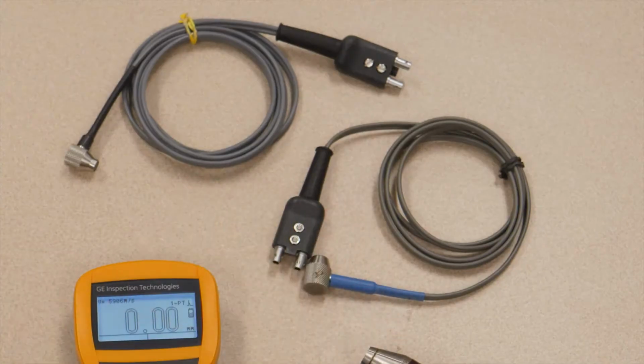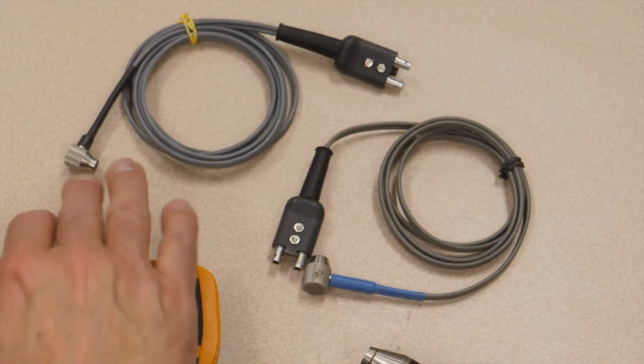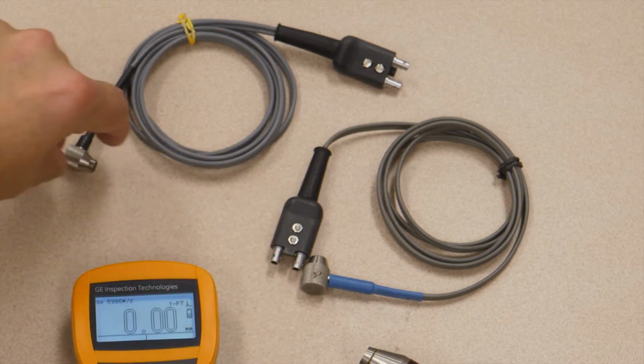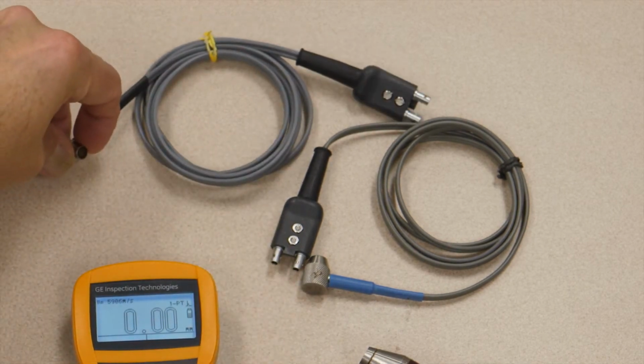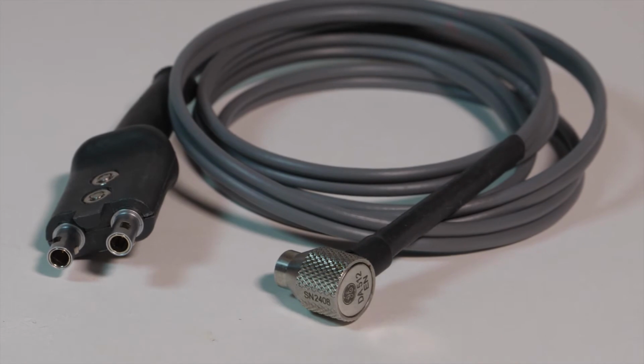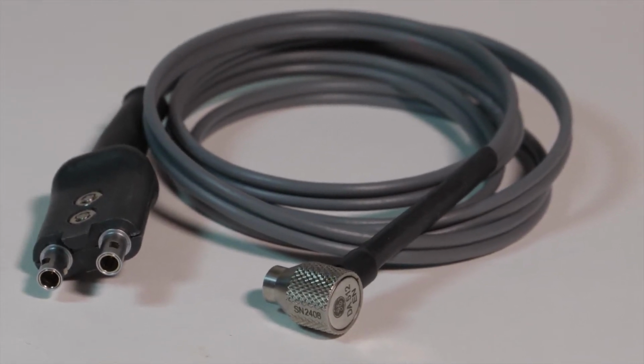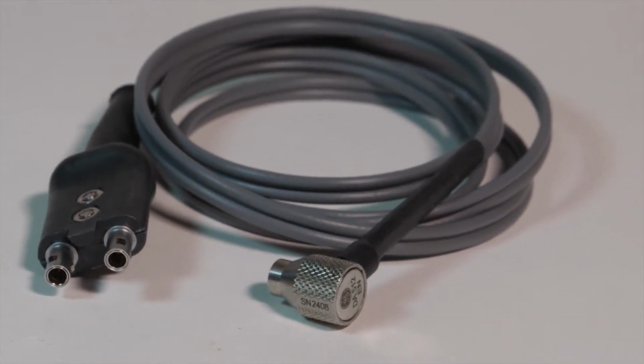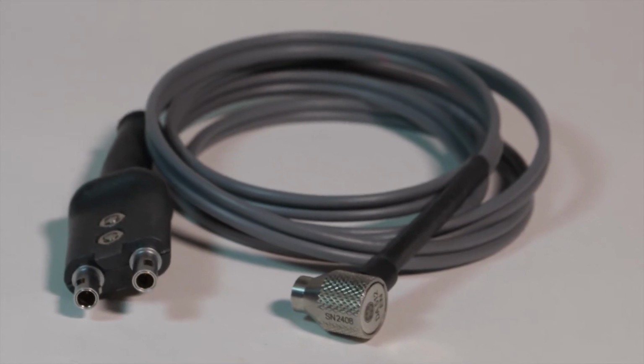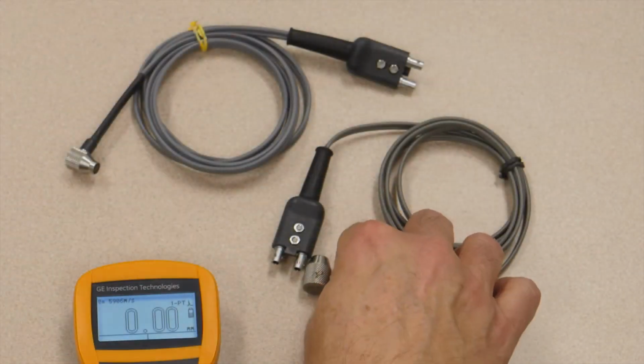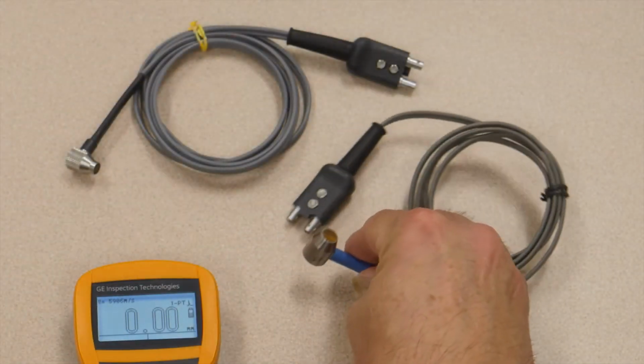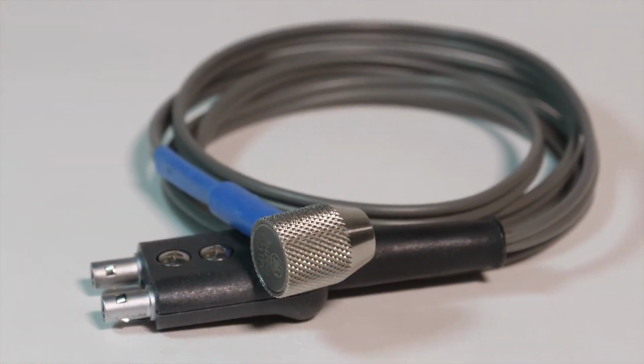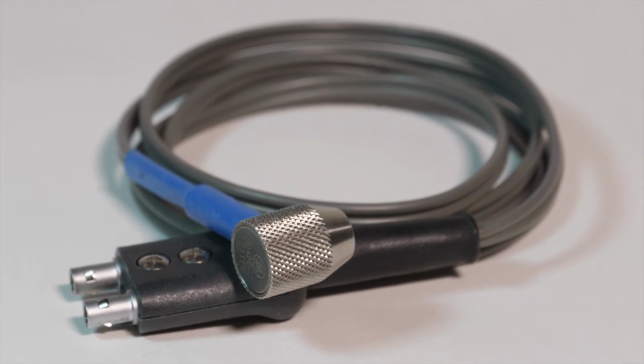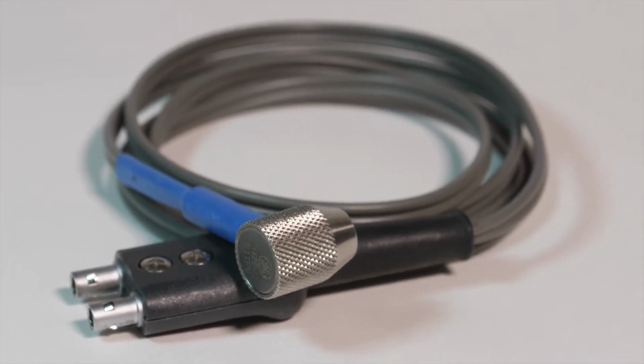And we have our fingertip probes that are commonly used. The DA312 has a very small contact area, ideal for reaching into tight spaces, ideal for reaching into pits on the surface of materials to take measurements of remaining wall thickness. Another common fingertip probe is the FH2E, a little bit bigger contact area, a little more versatile. You can work with thicker materials easily with that.